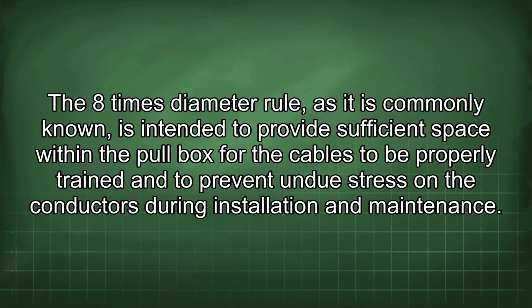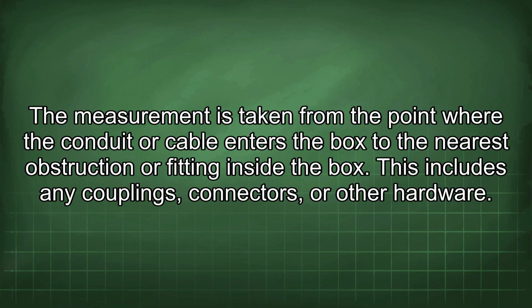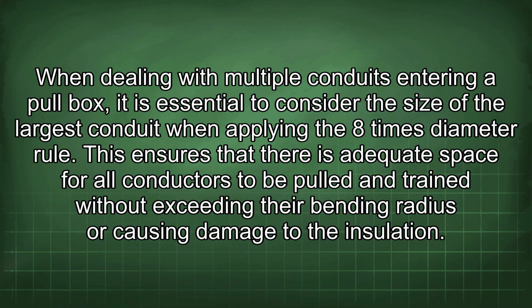The 8 times diameter rule, as it is commonly known, is intended to provide sufficient space within the pull box for the cables to be properly trained and to prevent undue stress on the conductors during installation and maintenance. The measurement is taken from the point where the conduit or cable enters the box to the nearest obstruction or fitting inside the box. This includes any couplings, connectors, or other hardware. When dealing with multiple conduits entering a pull box, it is essential to consider the size of the largest conduit when applying the 8 times diameter rule.